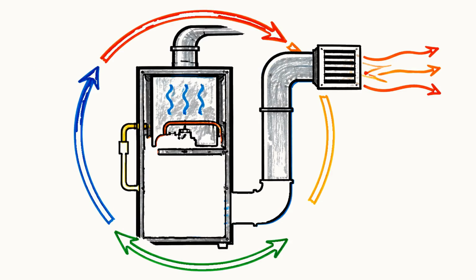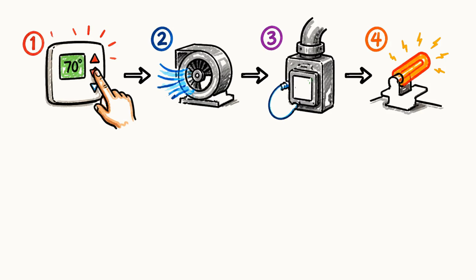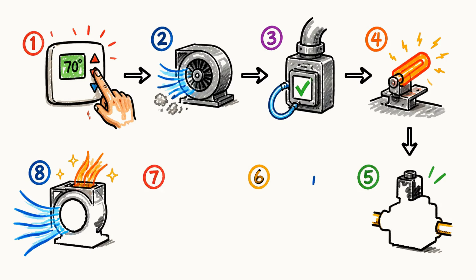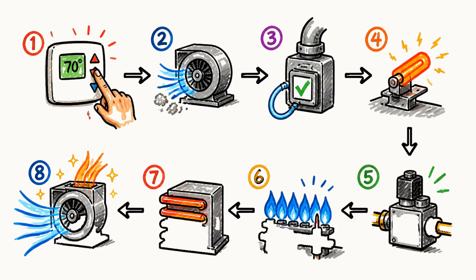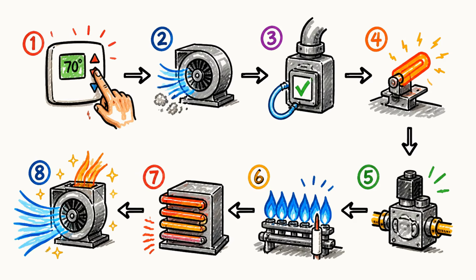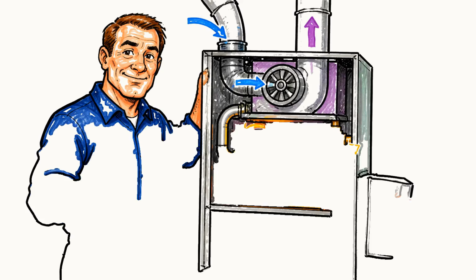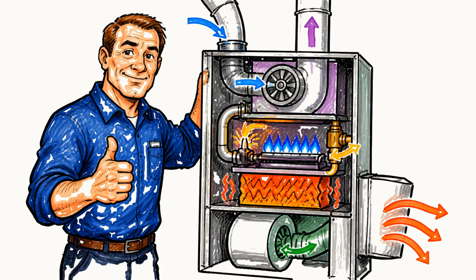That is the full cycle for a gas furnace. Call for heat, clear the air, prove the draft, light the igniter, open the gas, confirm the flame, warm the metal, move the air, and sweep the leftover heat on the way out. Every furnace you have ever stood next to runs some version of those steps.